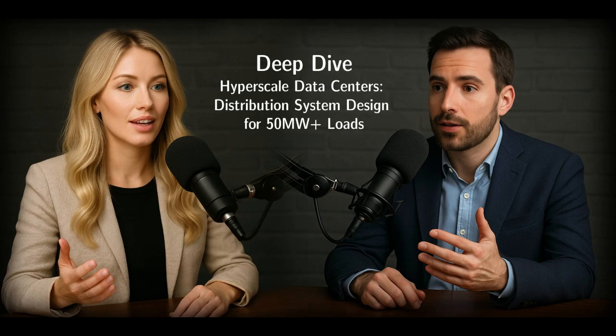Okay, so 12.47 kilovolt has its niche, but clearly not for the 50 megawatt plus loads. What's the next logical step up? Where's that kind of middle ground for, say, 15 to 50 megawatts? The source material points towards 25 or 35 kilovolt. Yeah, that 25 to 35 kilovolt range often hits a sweet spot. It offers some really significant technical advantages over 12.47 kilovolt.